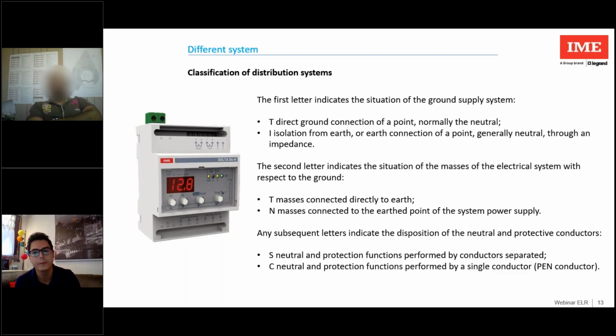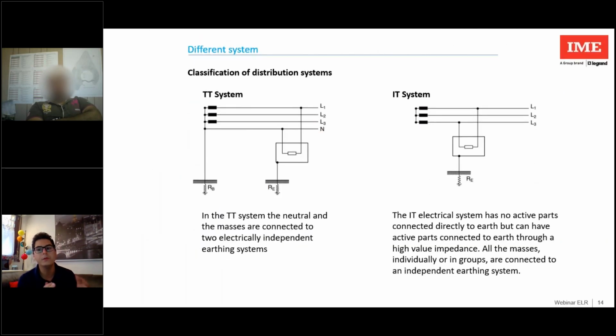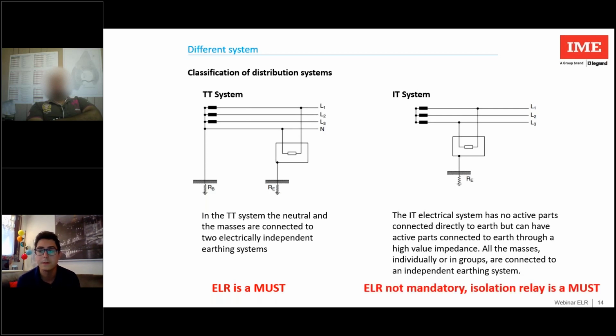Let's go in depth for a moment. In the TT system, the neutral and the masses are connected to two electrically independent earthing systems. In the IT system, however, there are no active parts connected directly to the earth, but we can have active parts connected to earth through a high value impedance. All the masses are connected through an impedance to an independent earthing system. In the first case, the TT system, an ELR is a must. In the second case, instead, an isolation relay could be enough.